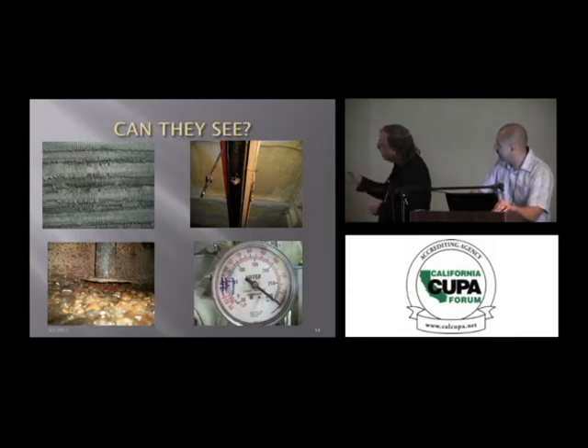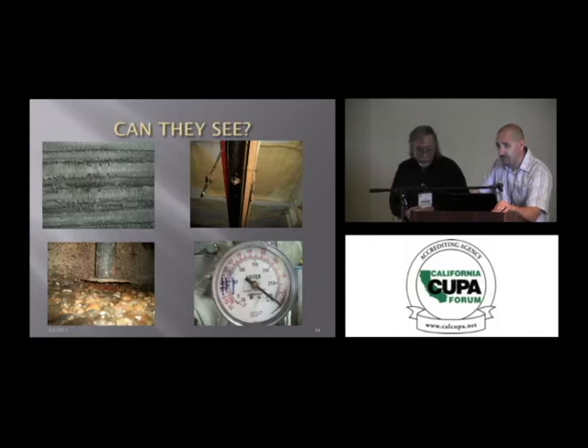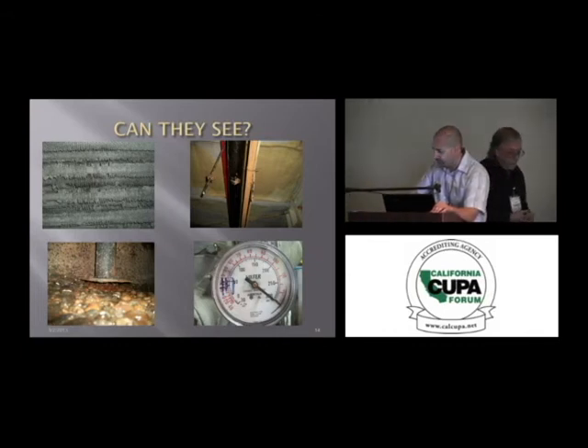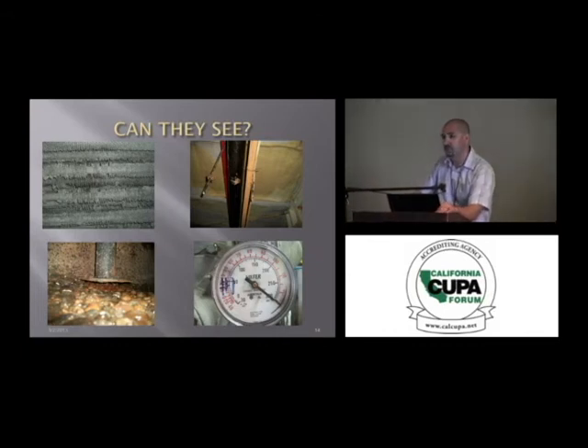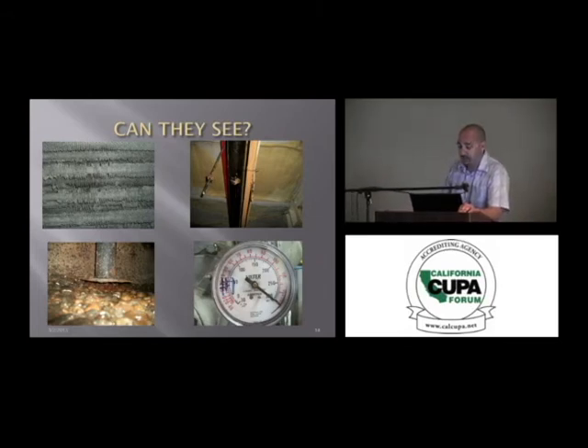We even run into this in production facilities where they're using sodium hypochlorite or other things to clean their floors, CIP chemicals, etc. And that will go to the air intakes, get to the coils, and accelerate the corrosion. There was a facility where they're using, I think it was chlorine, and the coils were 12 years old, and they needed to be replaced. Not good.